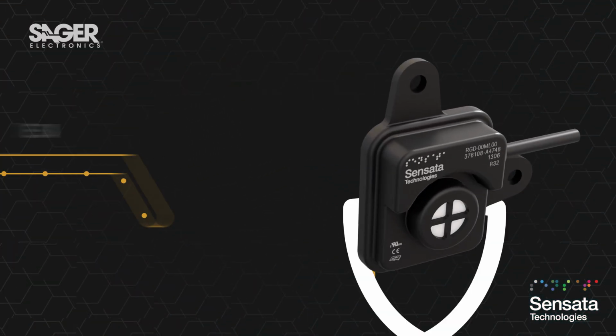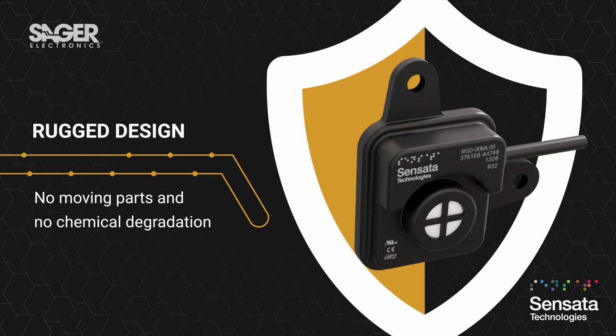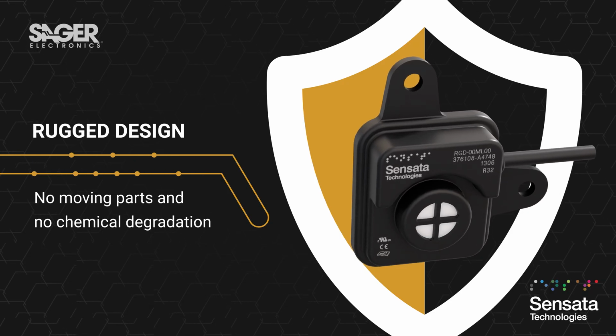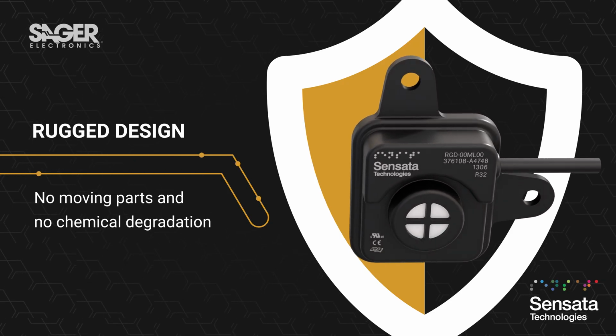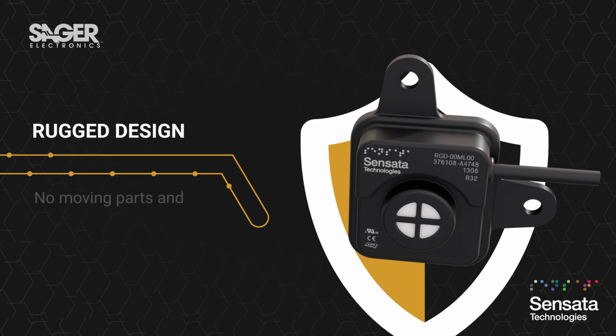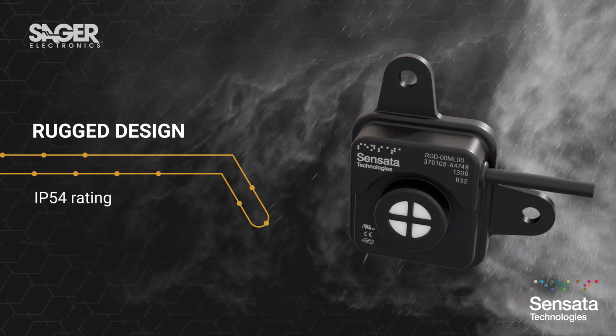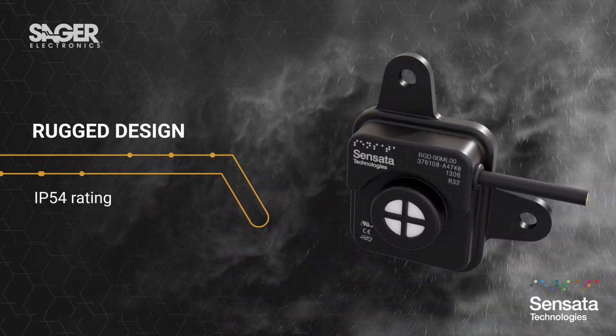By utilizing this acoustic resonance sensing technology, the Sensata RGD has no moving parts and no chemical degradation. With an IP54 rating, it can withstand substantial levels of dust and moisture in harsh environments.